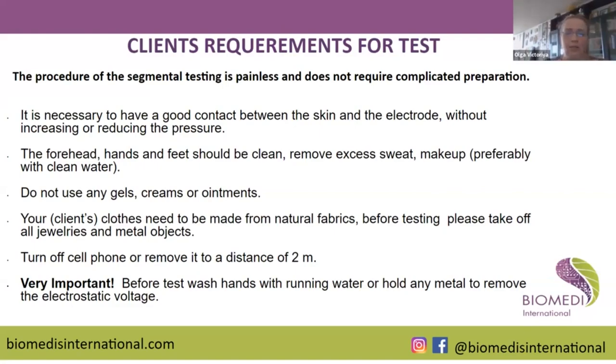Also, our client and operator, we both need to turn our cell phones off or put them at a distance of 2 meters from the testing area. Very, very important: before the test, you need to wash your hands with running water, both of you, or hold your hands on some metal. What it does is remove all the electrostatic voltage, so we will not destroy the device.